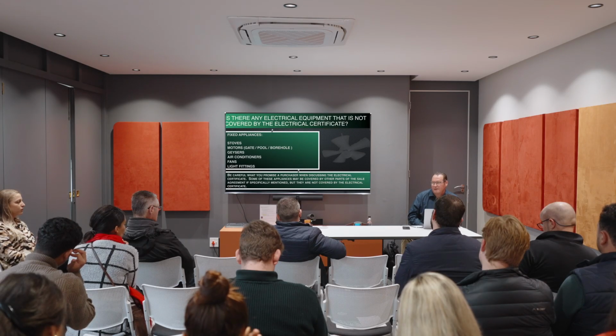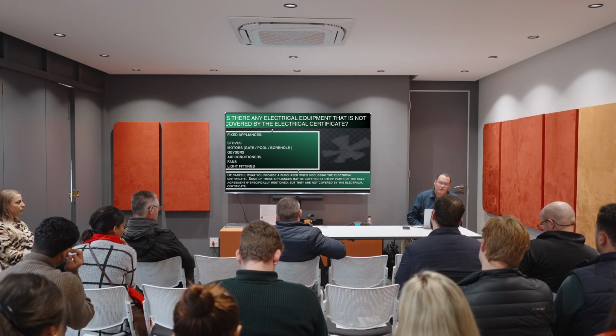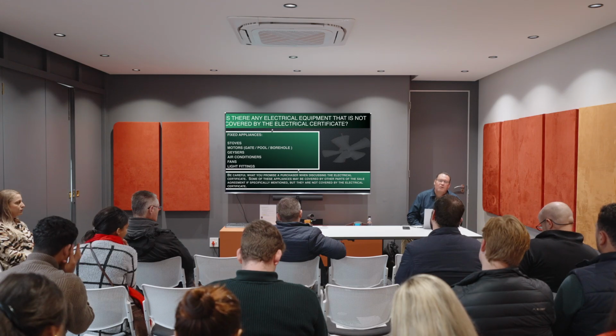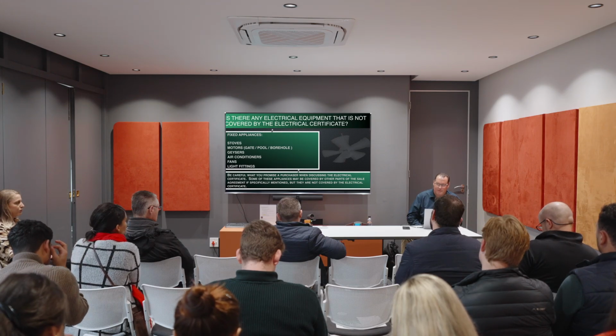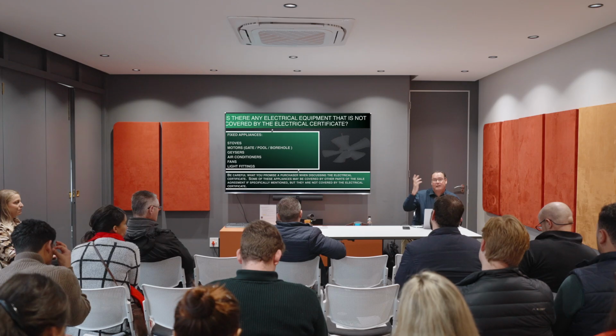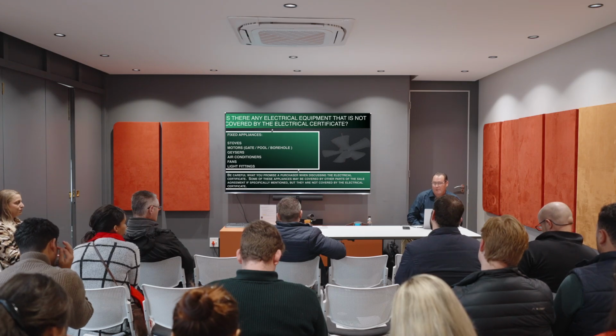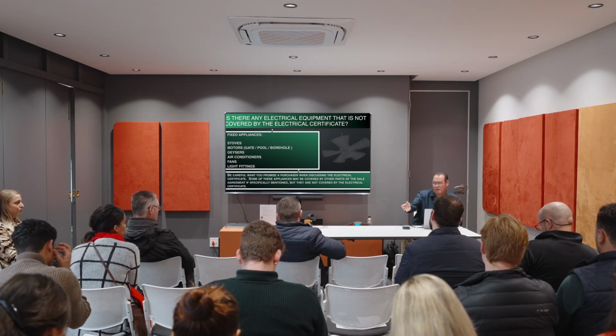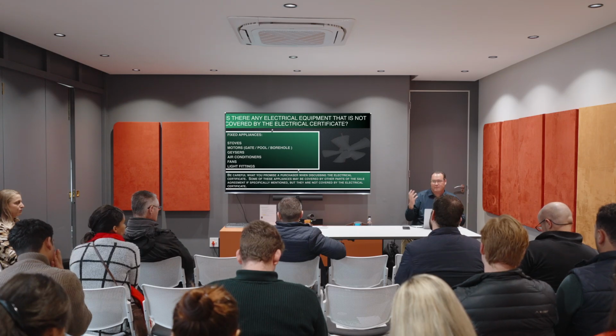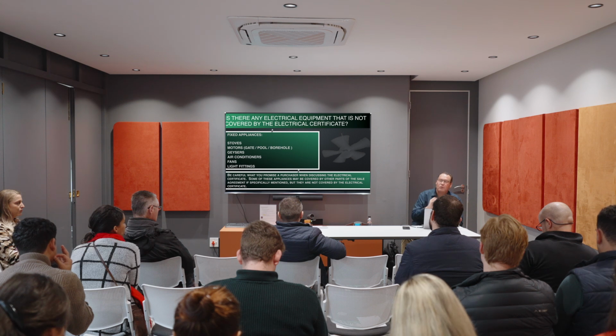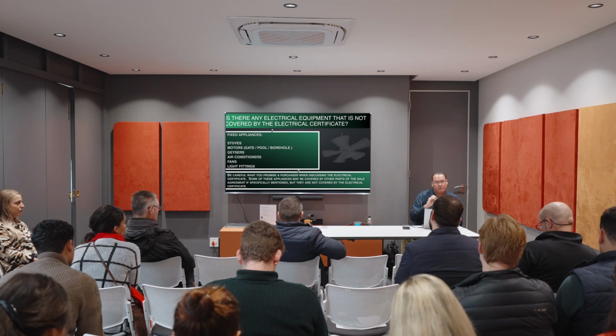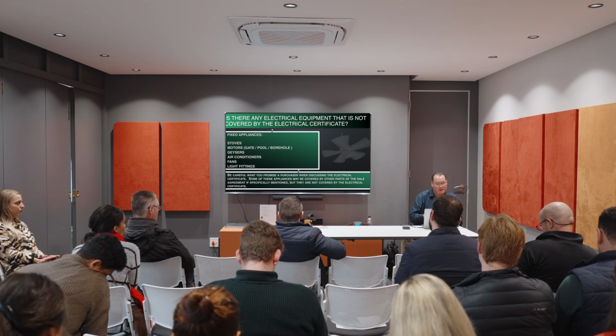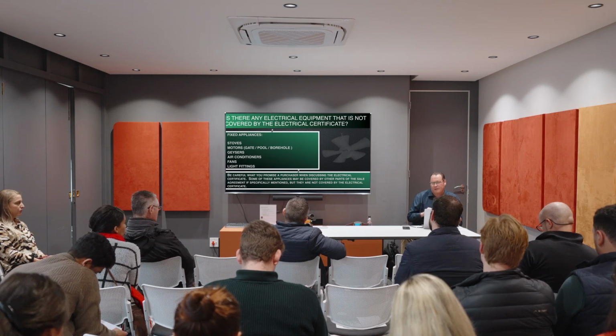Let's take light fittings. Light fittings are a fixed appliance. Strictly speaking, they do not have to be working for a certificate to be issued. Can you imagine the number of callbacks we would have if 15 lights in a house are not working? We'd be going back, client's going to contact you, then they're going to contact us. Everyone's upset with each other because, come on, the light should work. And so we do include light fittings because it causes too many questions and too much running up and down. It's expected that lights will come on.